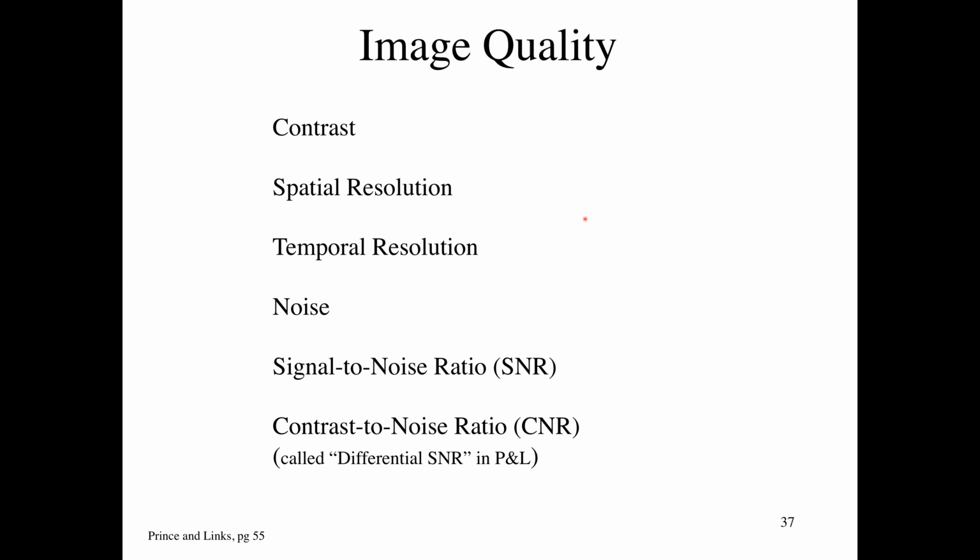Now I turn down my X-rays so that I do low dose imaging. And in some of my detectors, I'm getting 2, 3, 8 X-rays. So now I'm not that confident about how many are actually there because the counting statistics get worse, right? So that's a source of noise in CT. And then there's underlying electronic noise in all of this.